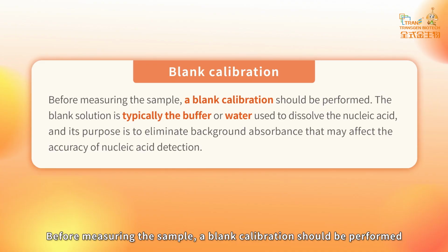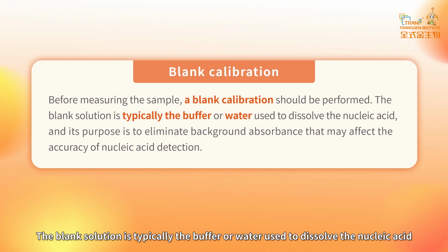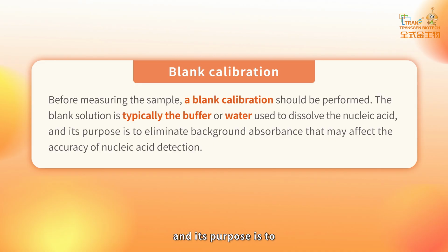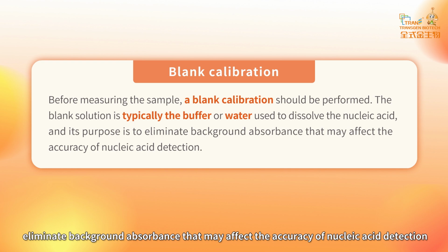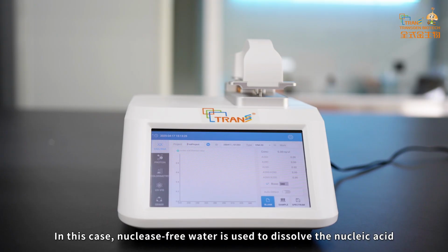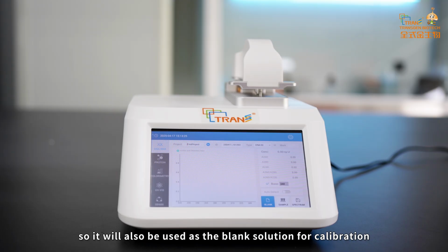Before measuring the sample, a blank calibration should be performed. The blank solution is typically the buffer or water used to dissolve the nucleic acid, and its purpose is to eliminate background absorbance that may affect the accuracy of nucleic acid detection. In this case, nuclease-free water is used to dissolve the nucleic acid, so it will also be used as the blank solution for calibration. The procedure is shown as follows.